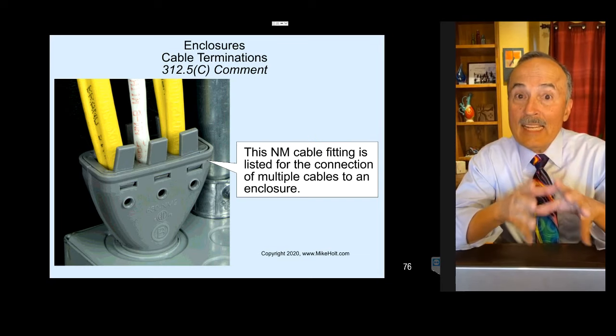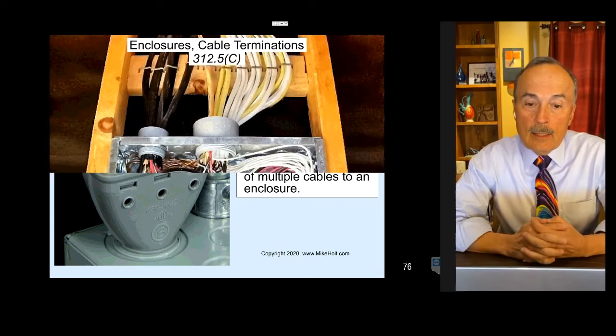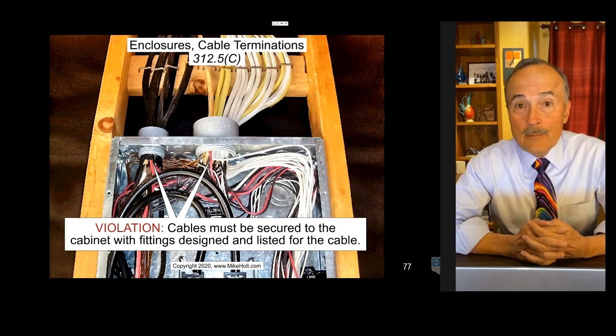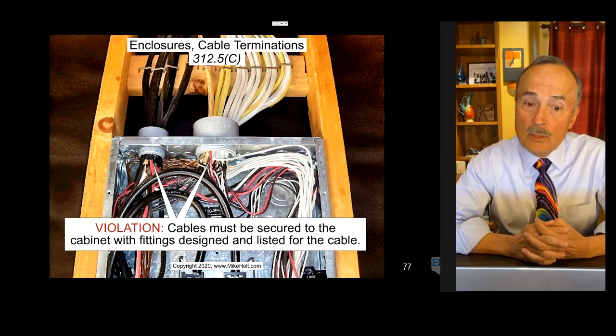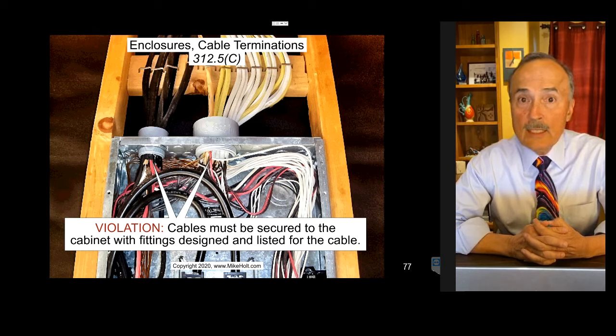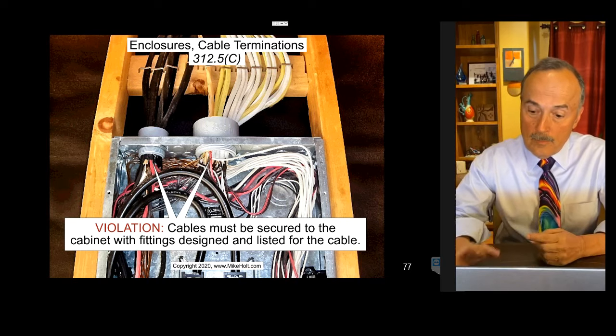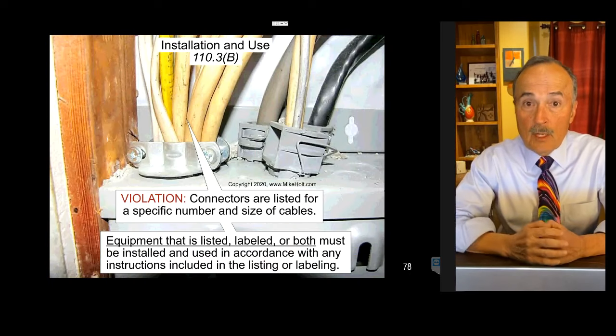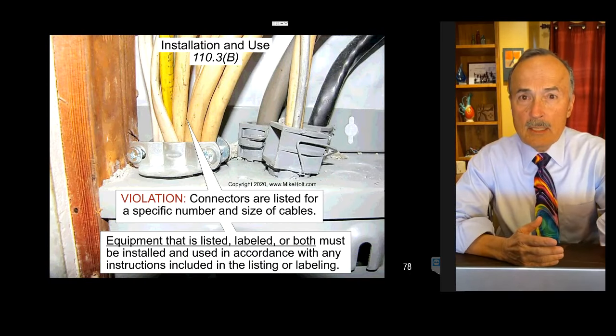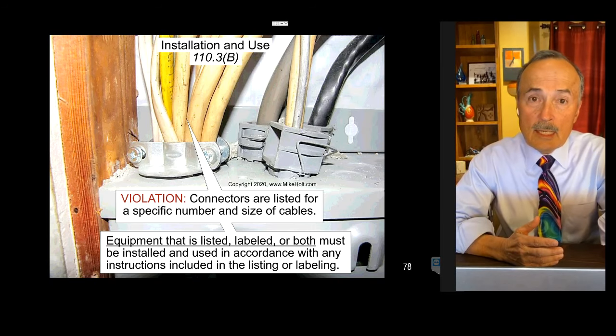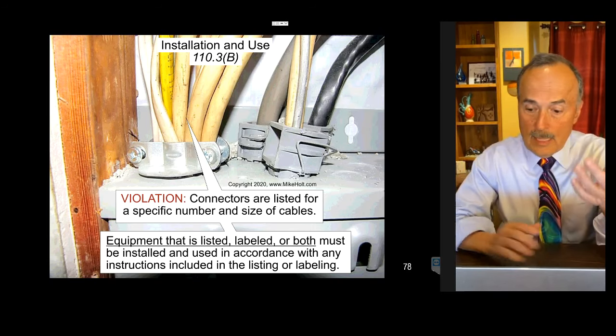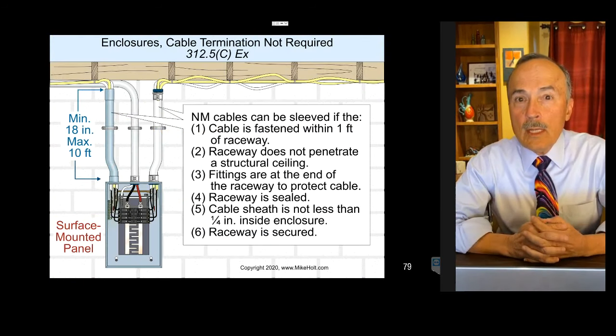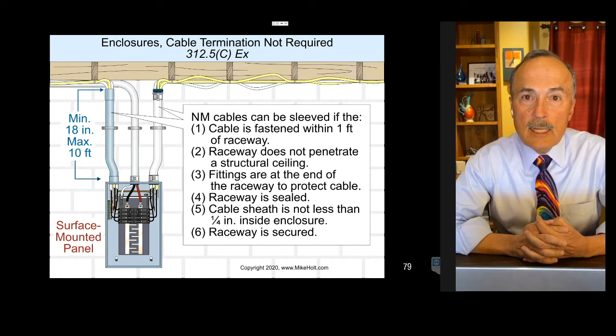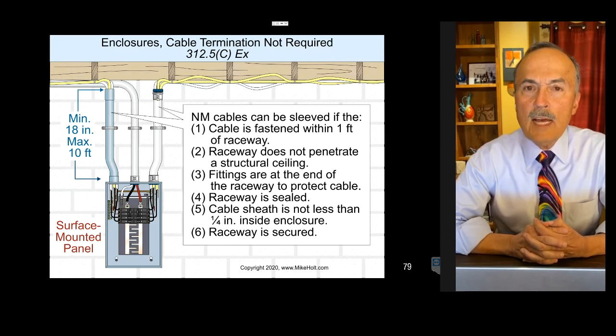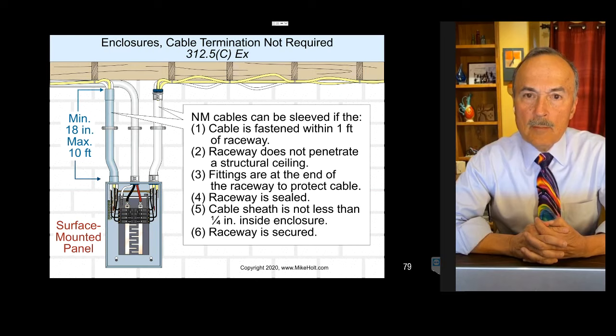Okay, well, here's an example. I don't know who makes this, probably Arlington. Here's a cool fitting that is specifically listed and identified for multiple cables. They'll tell you what size conductors, how many conductors. So that is fine. That's not fine, because the code says you have to terminate the cables with fittings identified and listed for the cable, and that's not legal. So there's an example of, no, that fitting, and of course 110.3(B) says you have to use fittings in accordance with the listing and labeling instructions, and of course that's not listed for that.